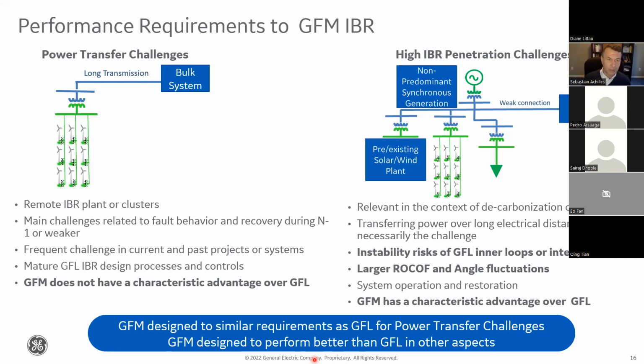So in that context, we propose here to divide some of the problems related to high penetration of inverter-based resources into two types. The one on the left is what we would refer to as power transfer challenges, where you basically have a plant, it could be a solar plant, a wind plant, or a number of plants in a remote cluster that connect through a long transmission line or system to a bulk power system. So this is one way of defining weak grid. This is one type of weak grid.